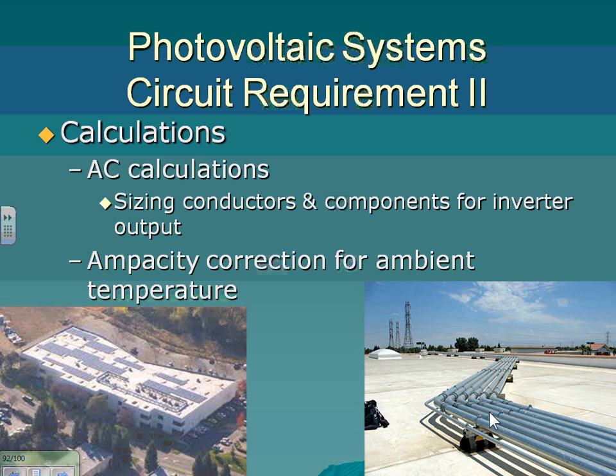AC sizing, a couple of things I'm going to talk about. The inverter output continuous load is the amps of the inverter times 1.25. For the DC part, they take the amps multiplied by 1.25 because of short circuit, and then multiply it again by 1.25 because of the continuous load. They want the conductor to be able to handle the short circuit of the panel without creating a fire. Take the panel on the roof: you grab the positive and the negative and short them, and you don't want the conductor to burn. That's how they size the DC part, multiplying twice by 1.25.